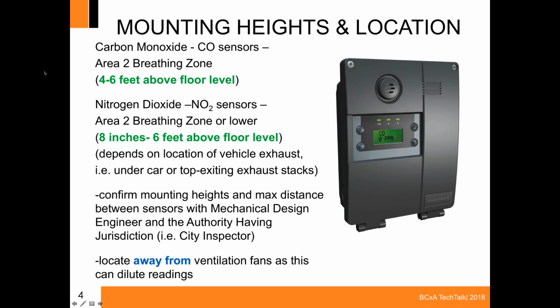So moving on to the mounting heights and the location, the carbon monoxide sensors go into the area's breathing zone, which is about 4 to 6 feet off the ground, whereas the nitrogen dioxide sensors are anywhere from 8 inches to 6 feet above the floor level. And what determines that is usually the type of diesel vehicles that are going to be in your garage. If it's more of a service vehicle that has top-exiting exhaust stacks, you're looking at higher elevations for the mounting height. And if it's more like just diesel cars, you're looking at lower ones. Typically, we see the NO2 sensors up near the ceiling because the NO2 rises.